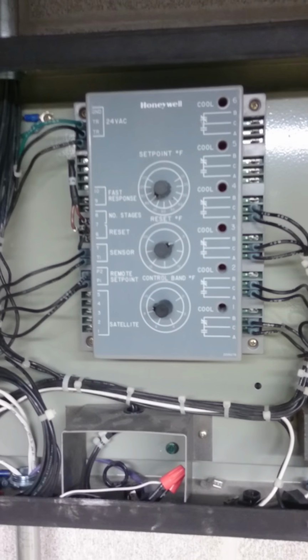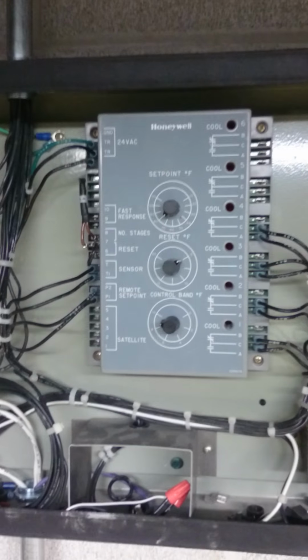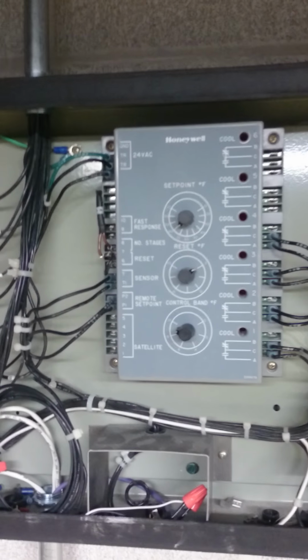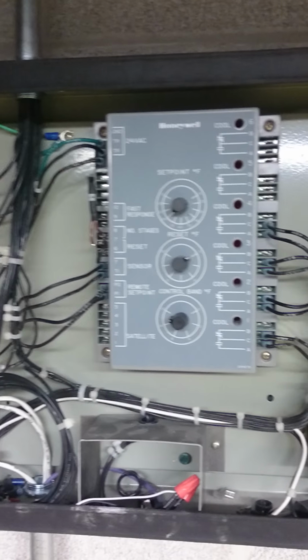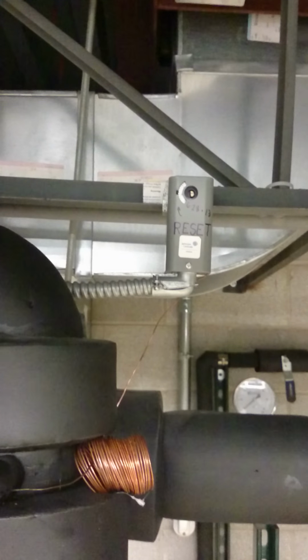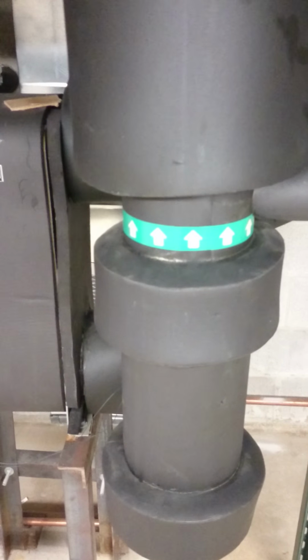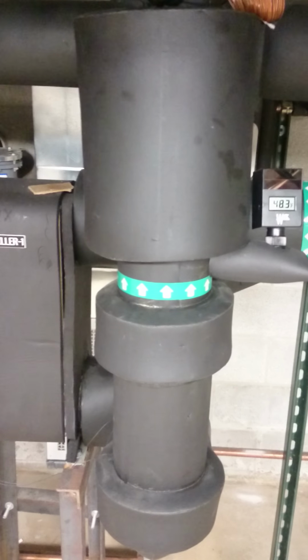So for the years that this was installed, maybe about 5 years, we've got 2 compressors that have never run on it. But before we were able to enable those compressors, also since it was installed, we're having problems with this Freezestat tripping. So this would be from the outlet water, and we do have water, not glycol. The outlet water from this heat exchanger was getting down close to the freezing mark and tripping this reset. First few times I came out here, everything was working great. Never seen anything below 40 degrees. It was always on a hot day.